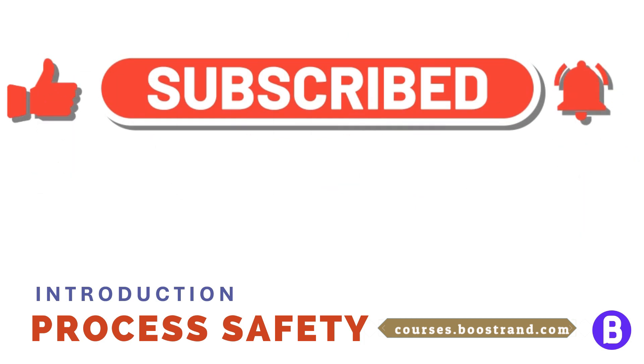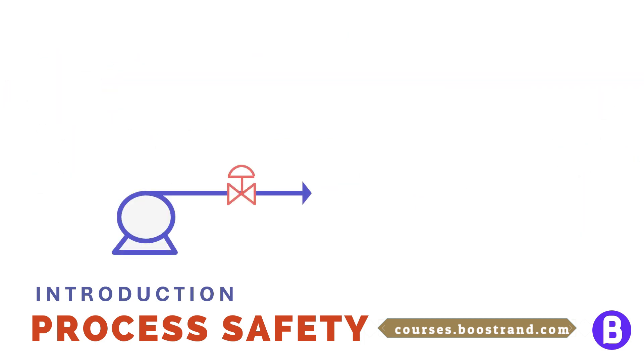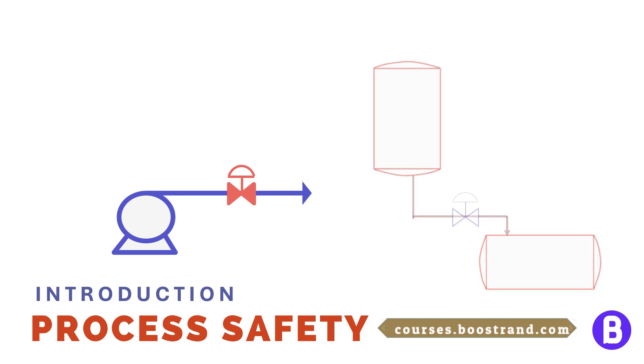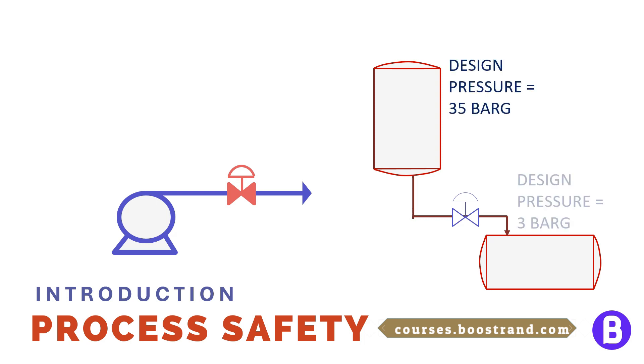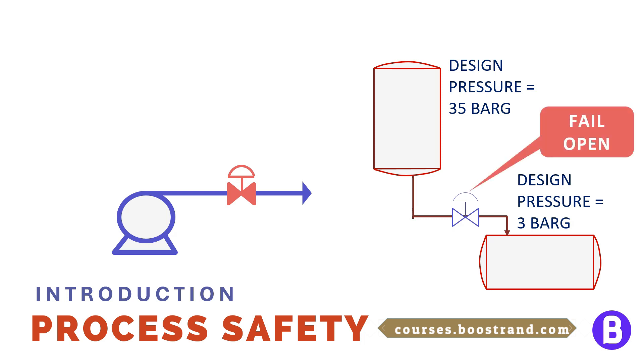For example, what if the valve at the pump discharge failed in the closed position — whether due to a false reading or mechanical failure? The upstream pressure shall increase. Is the upstream system ready for that pressure? Or what if the valve controlling the flow from a high-pressure system to a low-pressure system failed in the open position, meaning the valve is at 100% opening? How shall this excessive flow affect the downstream system?